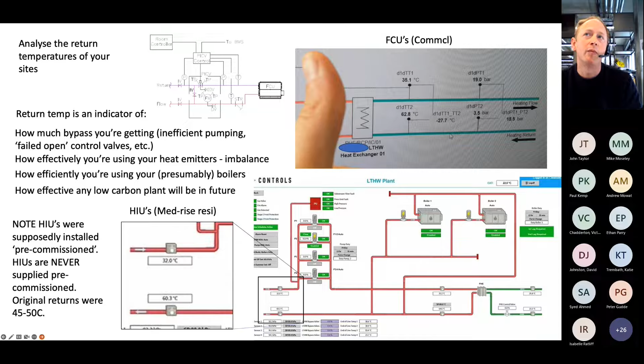Again, this is a site where the fan coils and the air handling are all designed to try and achieve a 30-degree delta. You're seeing that you've got a flow imbalance here. You are using more effectively the higher grade heat rather than the low grade heat, which is what you want to be doing. And the only way you get to usefully use that is by returning lower temperatures.